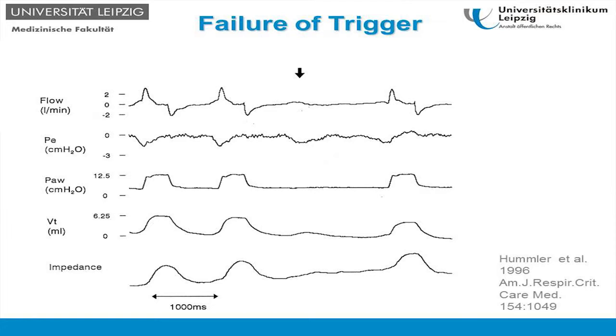If you increase the trigger threshold too high, we get a failure of the trigger. As we see here, the patient wanted a breath but didn't get one because the trigger threshold was too high, was not exceeded by the patient's effort, and no breath was initiated.